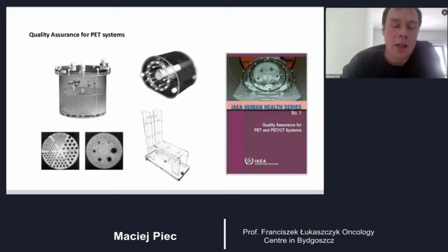NEMA body phantom, which in our center is used for accreditation tests. I don't think that it is necessary for basic tests, but it's good to have such a phantom if we want to be accredited, and we can also perform quality assurance in accordance with the NEMA standard. Manufacturers often declare certain technical parameters obtained from NEMA standard tests, so we can compare our measurements with reference values given by the manufacturer, and by that we can find out whether our equipment performs well. And another phantom is for the assessment of spatial resolution in air.